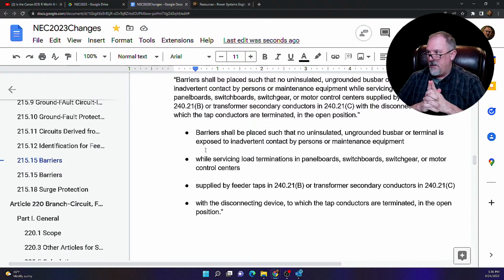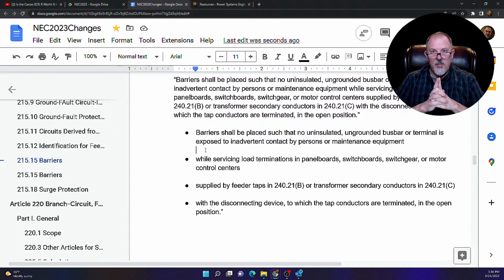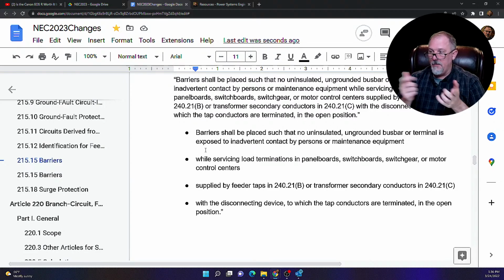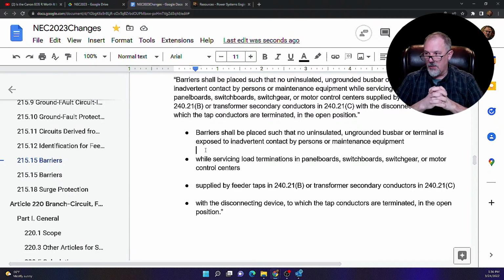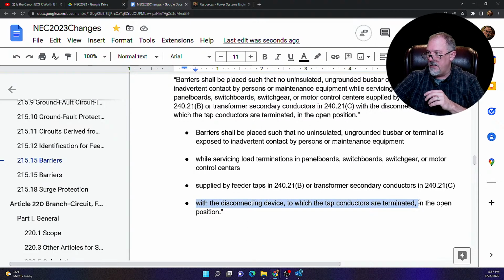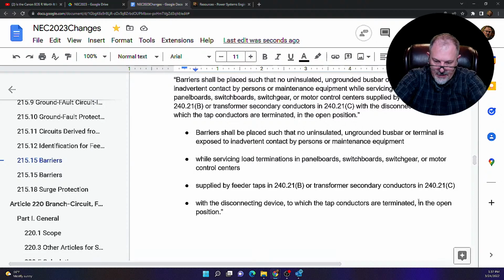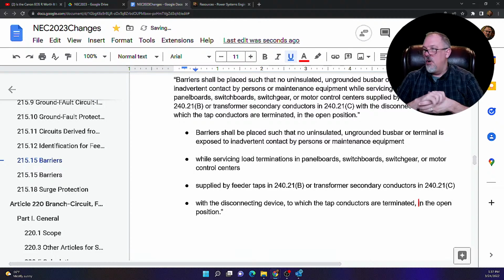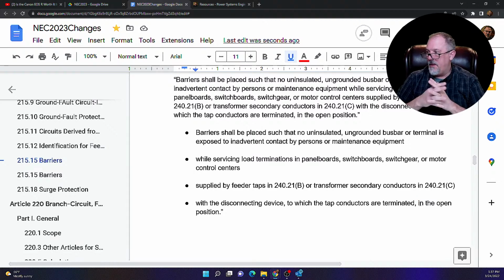Barriers. So we know we need barriers placed such that no uninsulated, ungrounded bus bar or terminal is exposed to inadvertent contact while servicing load terminations in panel board, switchboard, switchgear, or motor control centers supplied by feeder taps, when the disconnecting device to which the tap conductors are terminated is in the open position. I'm going to highlight that red because I think it should be: with the disconnecting device in the open position.